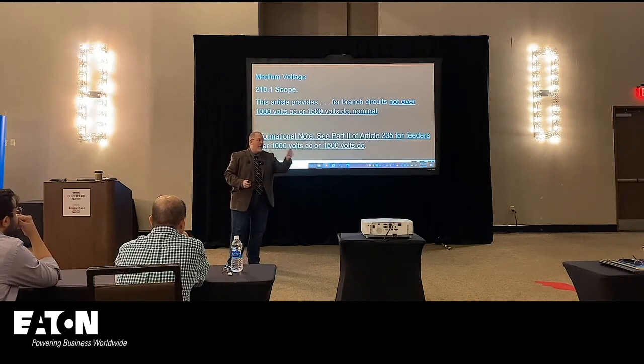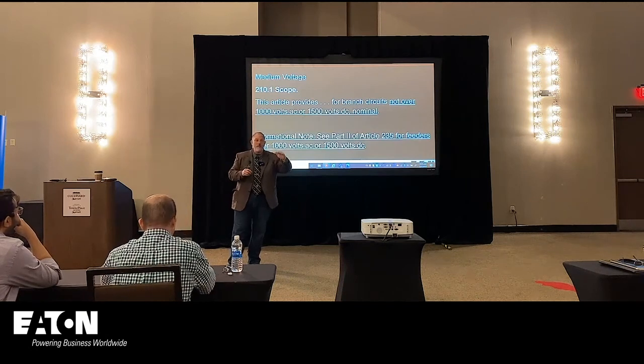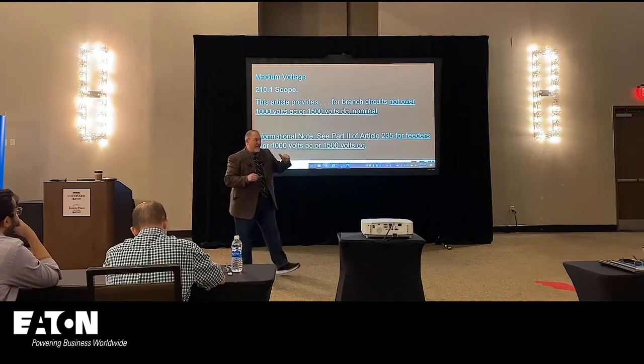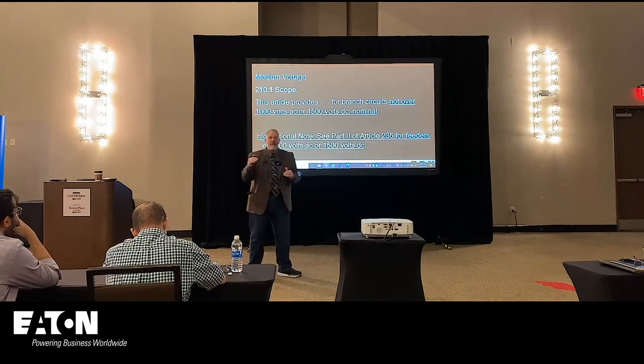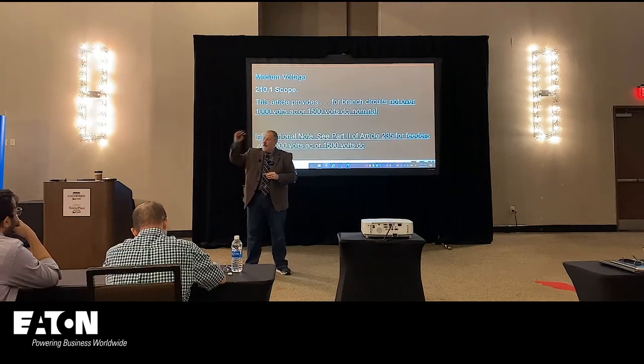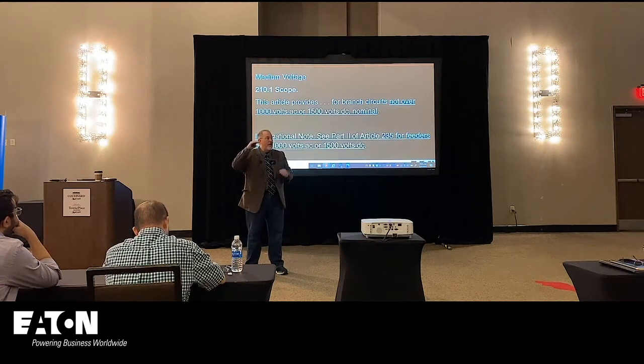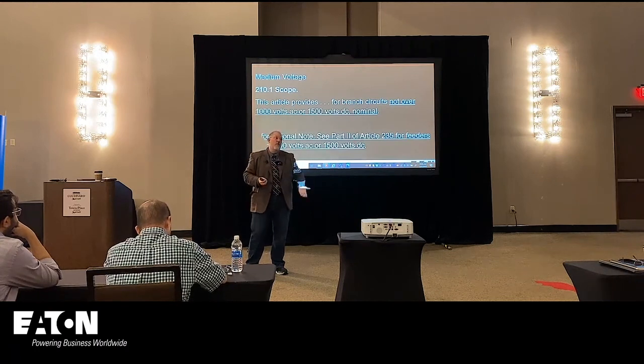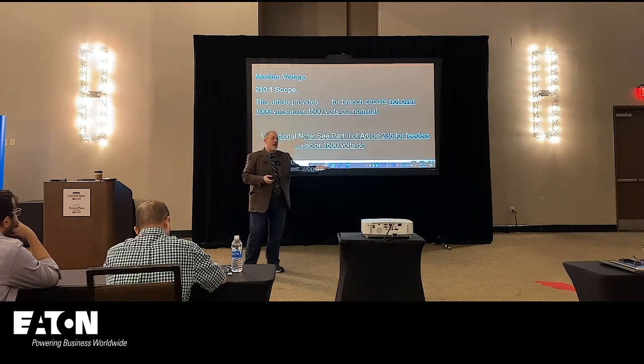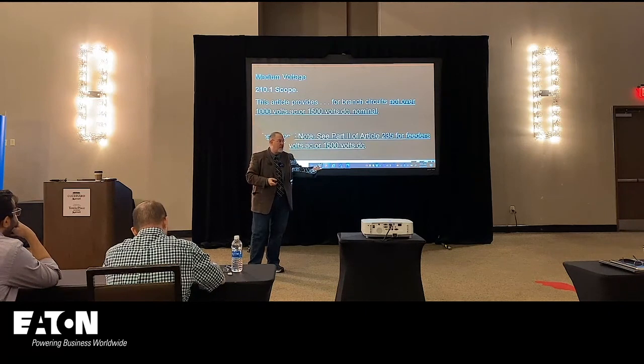235. And why? For the medium voltage, we established two lines in the sand: 1,000 volts for AC and 1,500 volts for DC. That was driven by IEEE standards and international standards. They established 1,500 volts for DC as that line in the sand for medium voltage. And what drove the 1,000 volts up over the last couple cycles was your photovoltaic applications, PV.